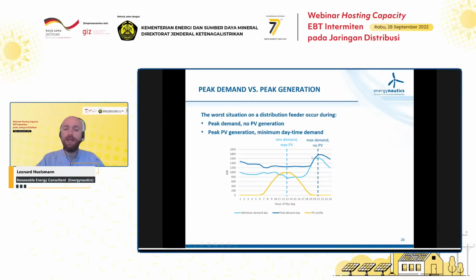And so this is illustrated here. So you might simulate during the peak demand time. Here maybe in Indonesia it might be similar, that this might be during the evening time or early evening time. And the worst situation in terms of PV generation would, of course, be at the middle of the day, when there's maximum PV production in combination with a low demand, which would then result in the maximum reverse power flows.